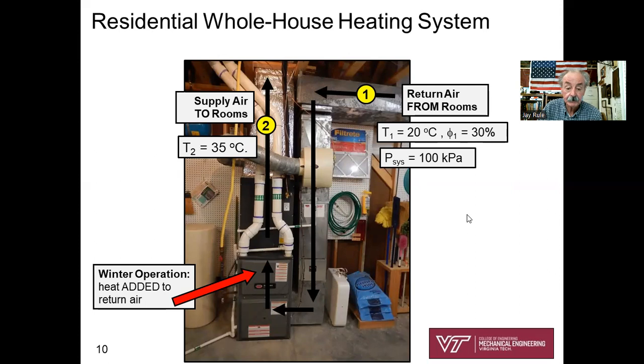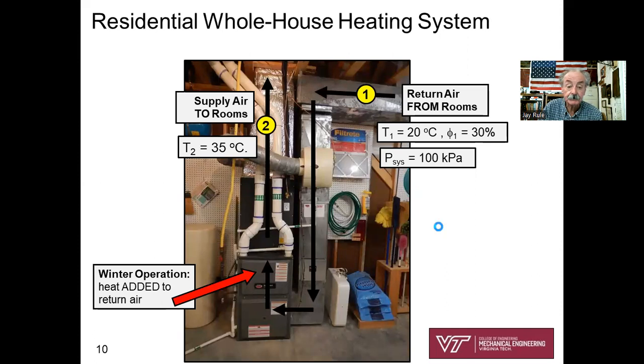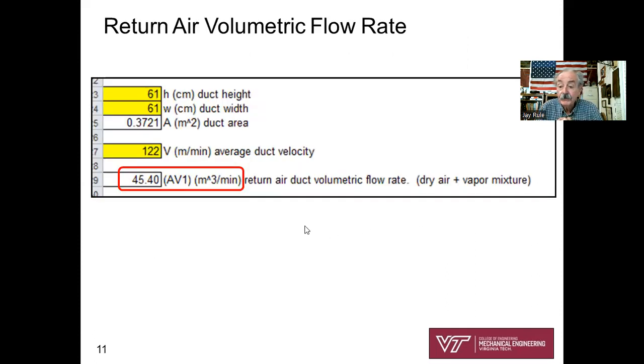Let's start with a sketch — I'll use the photograph. State one is the return air from the rooms coming in and making a 180-degree turn; here we add heat for winter operation, going up to state two at 35°C. State one comes in at 20°C, 30% relative humidity, and 100 kPa system pressure. The volumetric flow rate is simply the cross-sectional area of the duct times the average velocity: 45.4 cubic meters per minute.